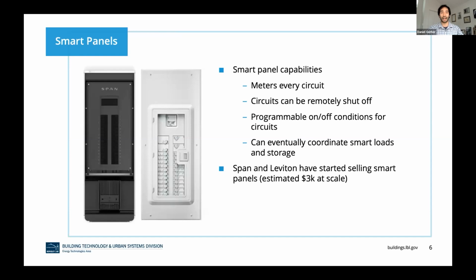At the top of this hierarchy we have smart panels. Smart panels do not avoid the panel upgrade — you have to buy a new panel — but they do avoid the feeder upgrade. So they're appropriate for cases where the feeder upgrade is unaffordable but the panel upgrade is okay.